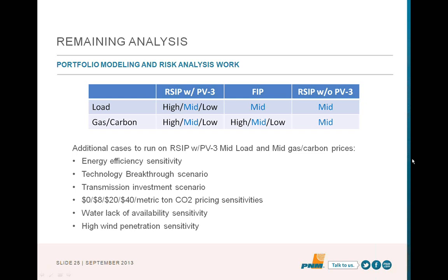Because I was actually thinking of the flip of that. So how close you can site to where you need. And it seemed to me that we had that discussion in the previous IRP. Yeah, and then that's another thing that happens when you shut down two units at San Juan. You've opened up an opportunity to site a generation resource at an existing generating site without having to incur much, if any, transmission cost. So that's another thing that is how we've thought about transmission so far. I mean, when we're talking about a gas peaker at San Juan, it's because the transmission's already there. We're in a gas production basin. So it just feels like that's a good site.